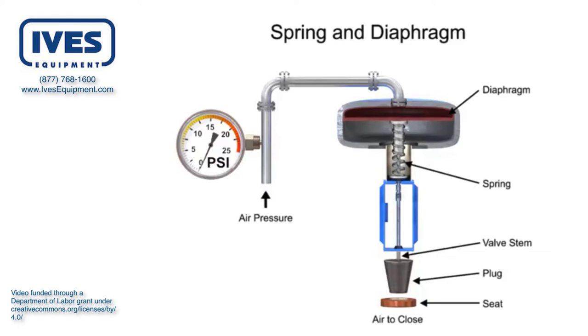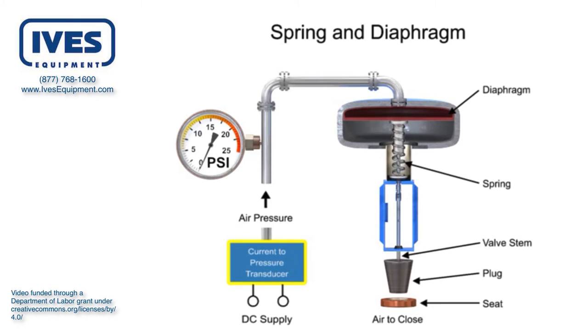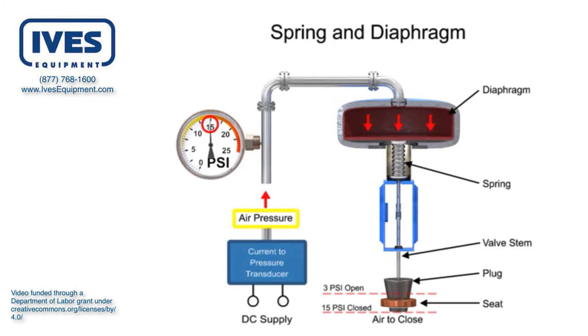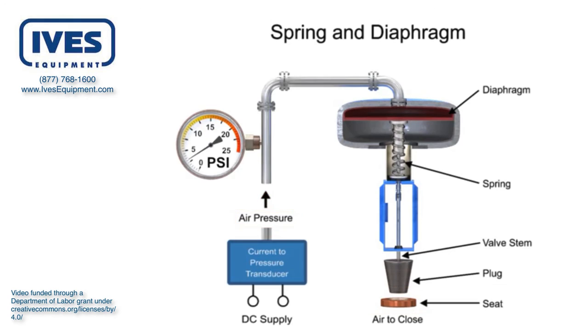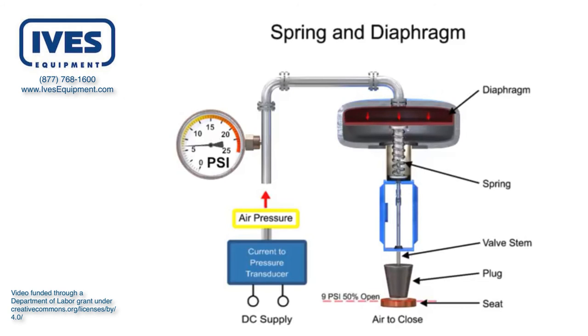To vary the position of the restrictor and flow through the valve, a current to pressure transducer can be used to provide a 3 to 15 psi signal to the diaphragm. At 3 psi the valve is maintained open and at 15 psi the valve is maintained closed. Pressures between the 3 to 15 psi range proportionally change the flow of the valve. For example, a pressure of 9 psi applied to the diaphragm moves the spring and valve stem to 50% of operating range.